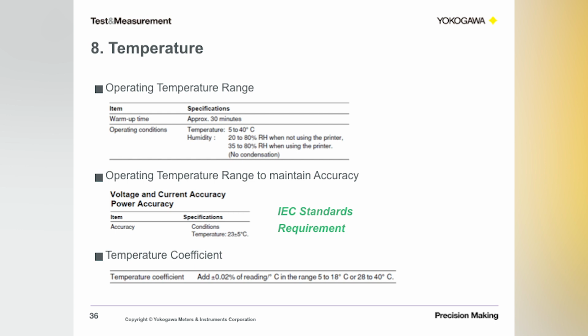Apart from just operating temperature range, IEC standards require that you state the temperature conditions under which accuracy is met. Usually that value is 23 degrees plus or minus 5 degrees Celsius. This is important because if the temperature of your measurement environment changes, then that could actually affect the overall accuracy of your measurement. Most manufacturers who comply with these standards will provide that specification, which is called the temperature coefficient, as I've shown out here. This is usually an additive addition to the accuracy of the operation under normal circumstances or temperature range, basically. So make sure you look for these specifications and account for them as you calculate your overall uncertainty.